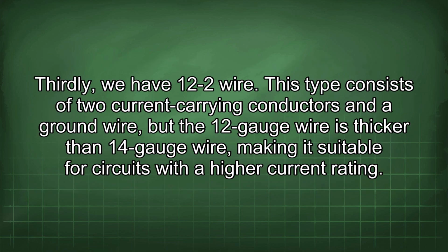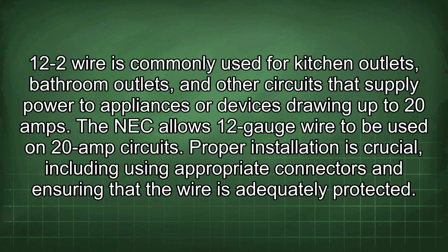Thirdly, we have 12-2 wire. This type consists of two current-carrying conductors and a ground wire, but the 12-gauge wire is thicker than 14-gauge wire, making it suitable for circuits with a higher current rating. 12-2 wire is commonly used for kitchen outlets, bathroom outlets, and other circuits that supply power to appliances or devices drawing up to 20 amps. The NEC allows 12-gauge wire to be used on 20 amp circuits. Proper installation is crucial, including using appropriate connectors and ensuring that the wire is adequately protected.